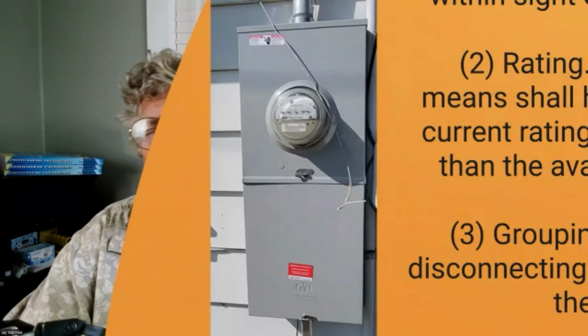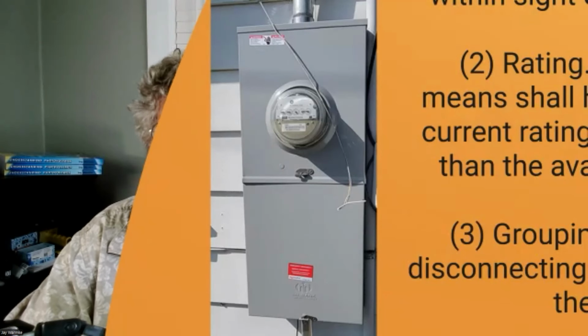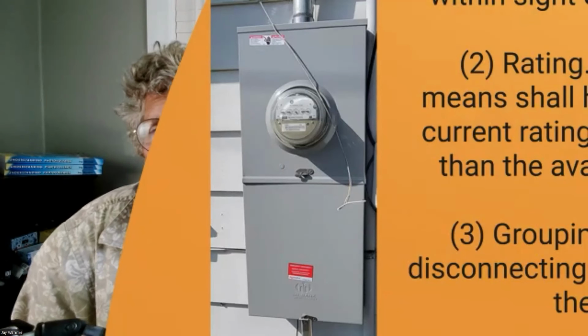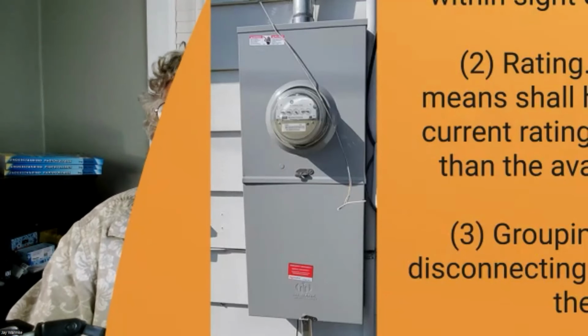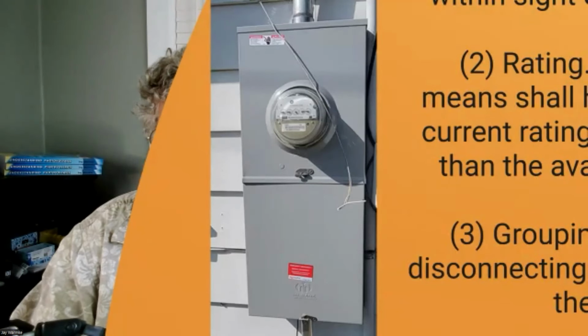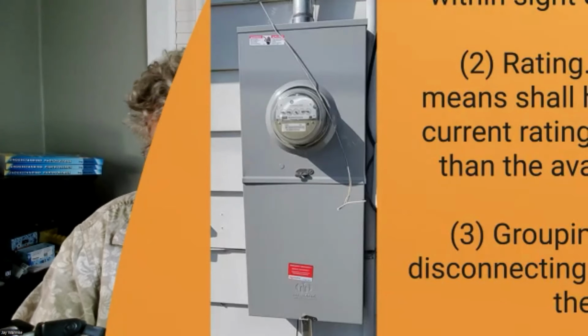Okay, so I always thought that was a bit redundant, because if you pulled the meter or you disconnect from your utility, the inverters are supposed to recognize that the grid is down and shut off. But the AC disconnect is there, I guess, as an additional safety matter. So it's out there. Well, what happens if you've got battery backup or sunlight backup with Enphase? If you now have turned off the grid, well, it goes into standalone mode, which means the smart switch disconnects you from the grid, so you're not going to backfeed, and now you're generating power and the house is still live.